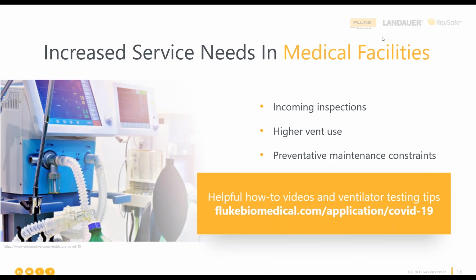All right, so along with all of this increase in production and increase in need in medical facilities around the world, let's just focus back in for a minute on how these ventilators that were just produced, just shipped, just delivered to the medical facility, what kind of additional testing needs happened. And it actually began back in the factory where these ventilators were being developed. So there was the design validation testing, and there was also final assembly testing in the production line, because that's the first time that all the pieces parts were put together into a supposedly ready for use ventilator that could then be shipped out to the hospital.